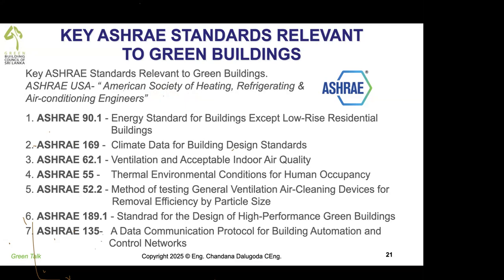There are about 100 standards, out of which few of these standards are used for green buildings. The main standard that we use in green buildings is the ASHRAE 90.1, energy standard for buildings except low-rise and residential buildings. Of course, we have 90.2 for residential buildings. ASHRAE 169, climate data for building design standards. We'll go through those things. 62.1 is ventilation and acceptable indoor air quality. 55, thermal environmental conditions for human occupants, that is comfort standard, 55. 52.2 is air cleaning, air filter standard.